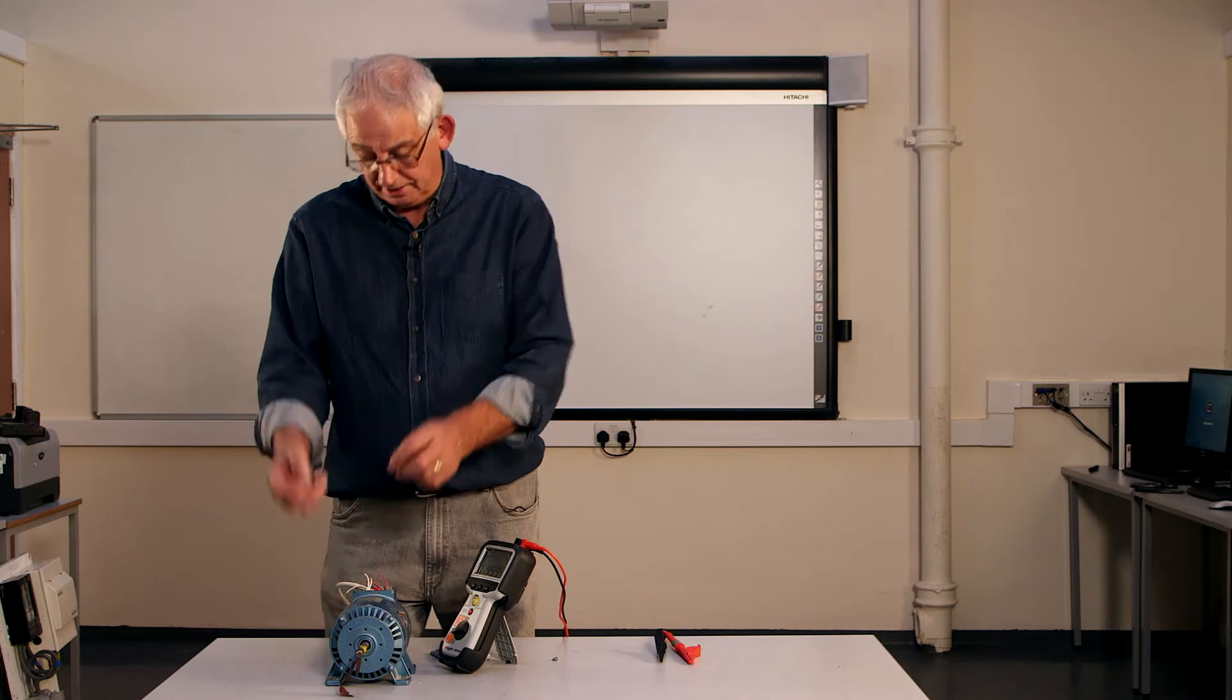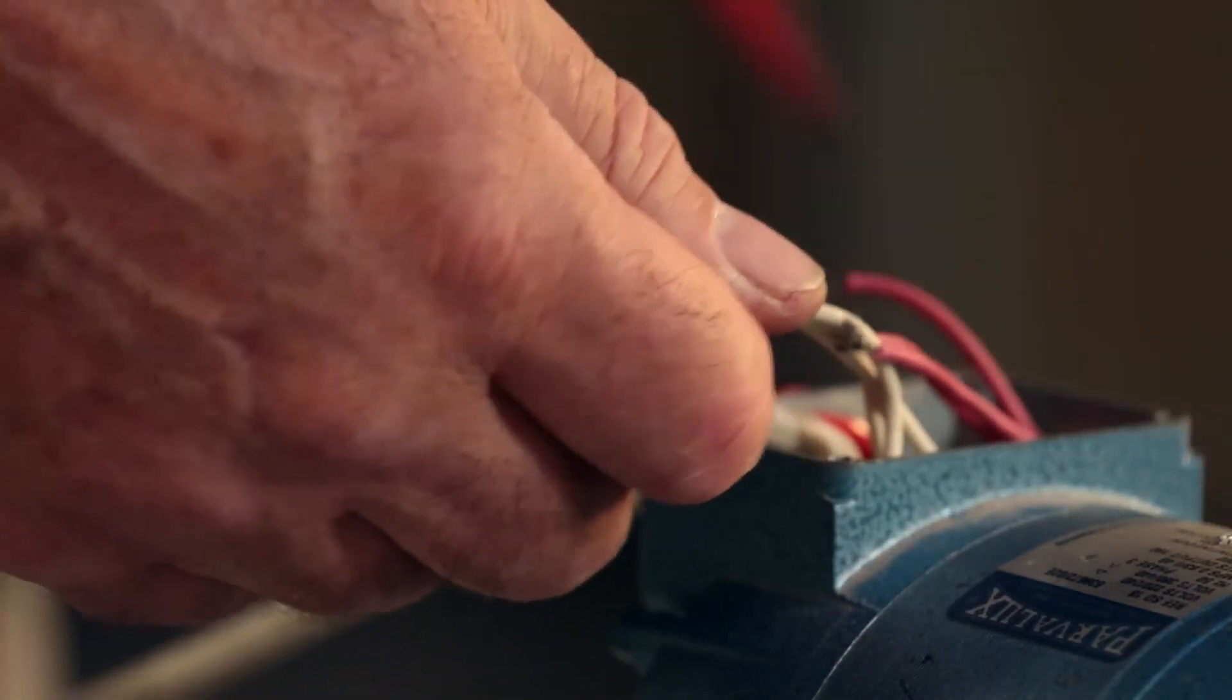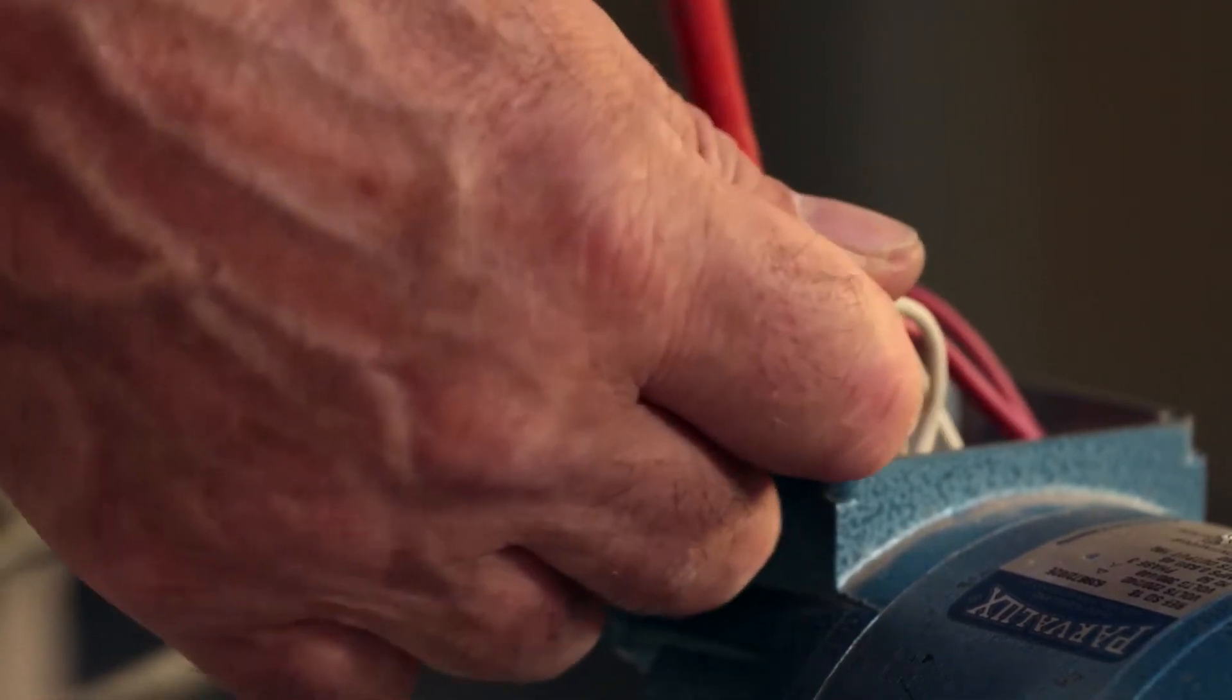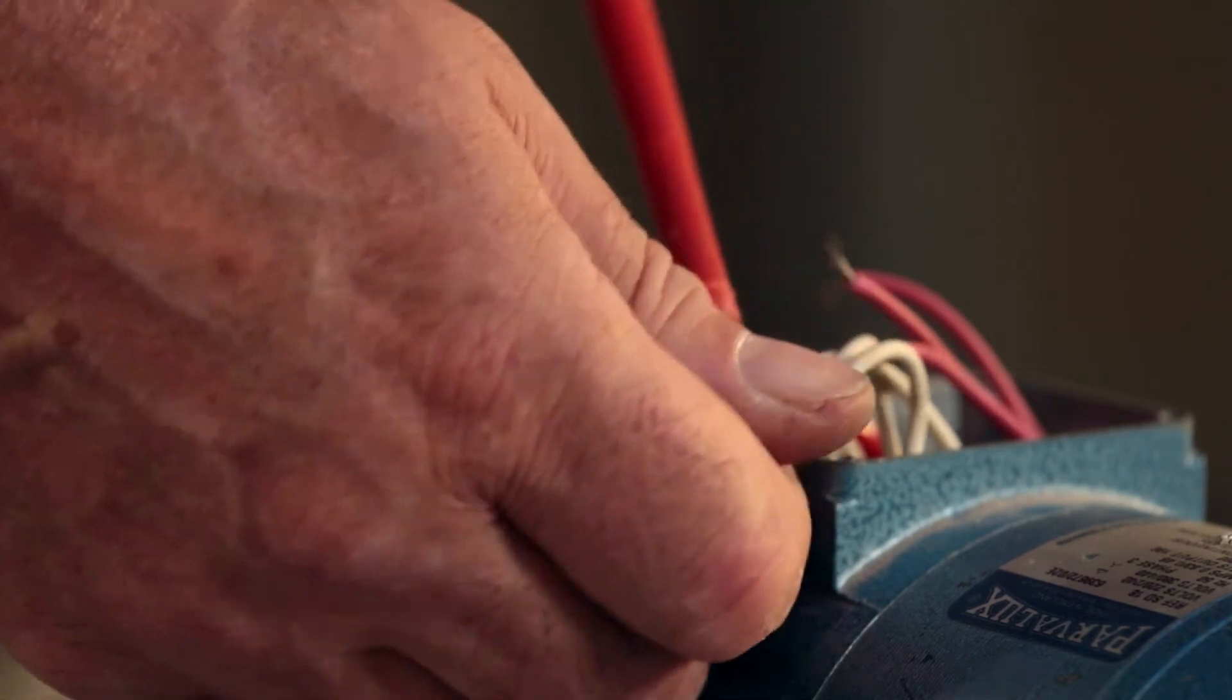So just need to connect the three. Doesn't matter whether I use the pink ones or the white ones, but I'll connect the three white ones together in a connector block. Make sure I do it up nice and tight because we don't want any loose connections. If we get a loose connection, we'll get a lot of heat. And then in the end, we'll have a fire in the motor, which is no good to anybody.